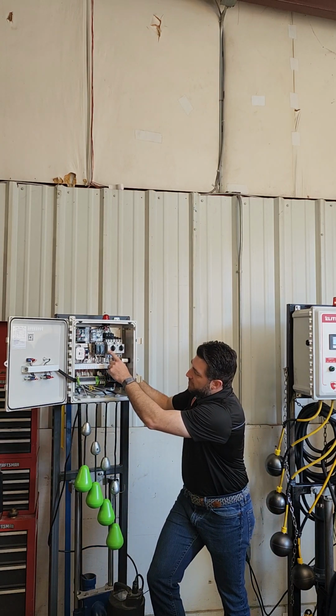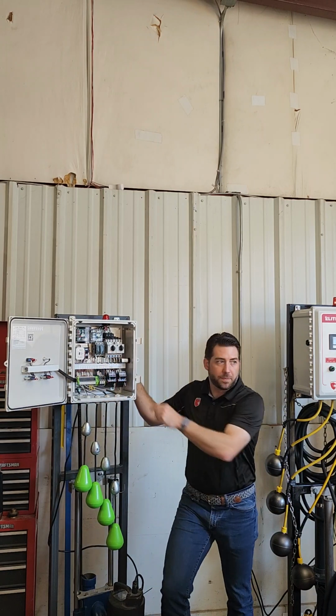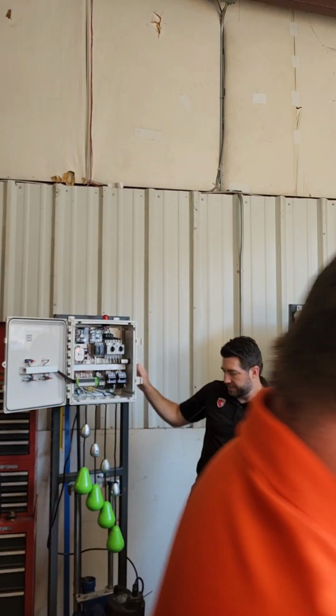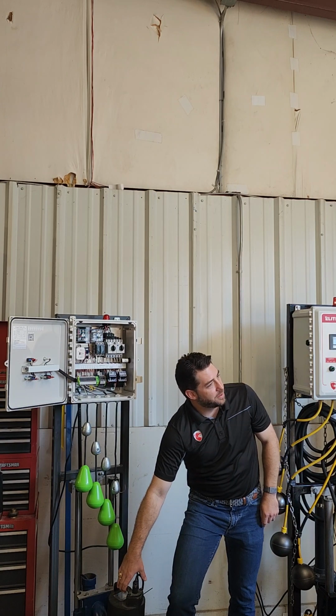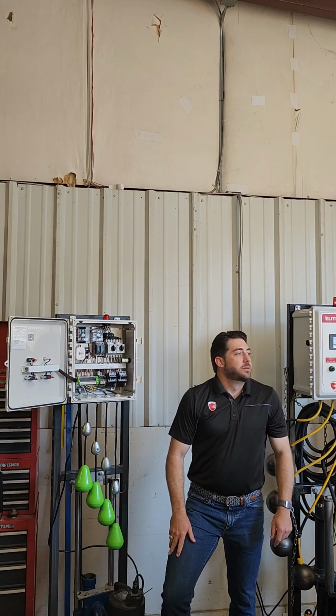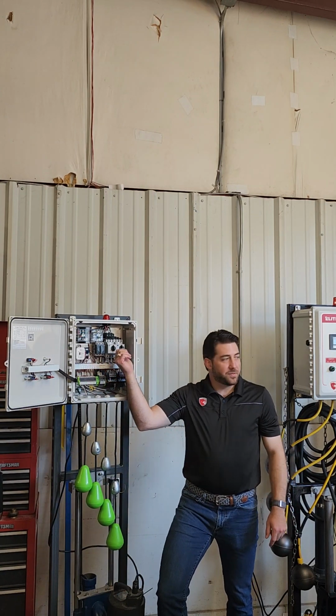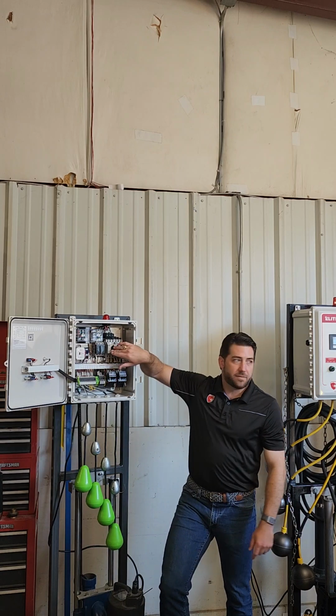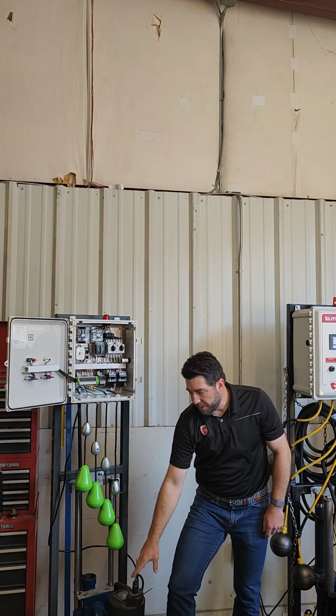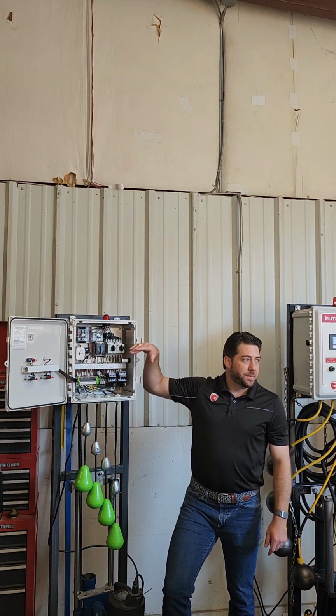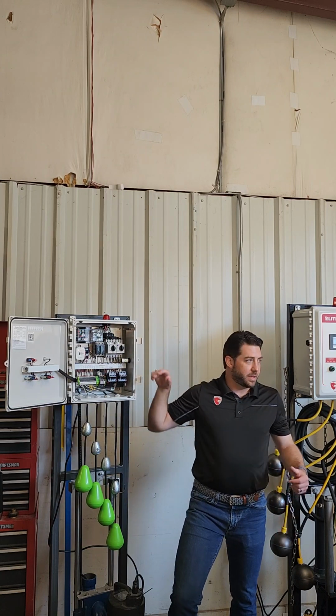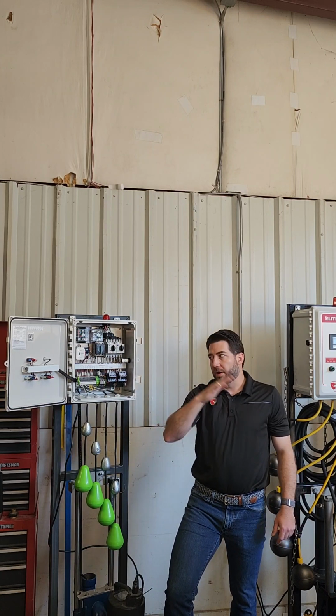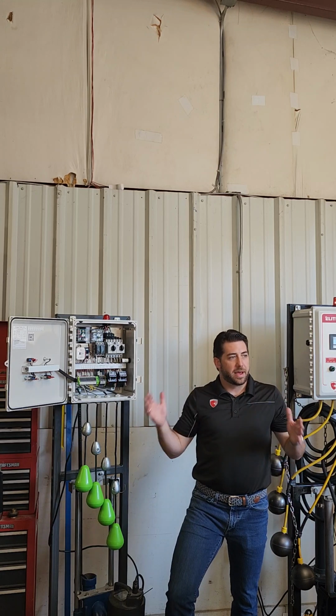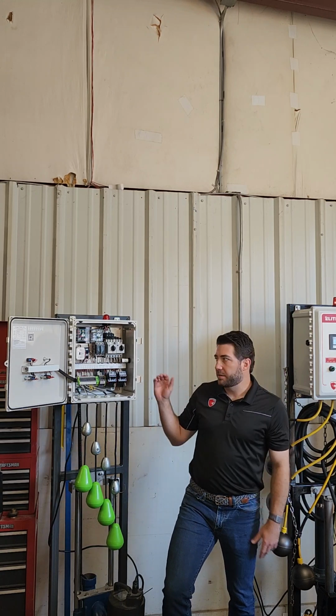So this is where you have the ability to adjust the amp range. And so you're going to match that to the full load amps on the nameplate of the motor. Not below or above, right? Right, you just match it. So it has the safety factor built in. You just dial it into whatever the rating is on the nameplate, and you'll be good. And so depending on the type of the overload, it depends how long it has to run over that amp draw before it actually kicks out.